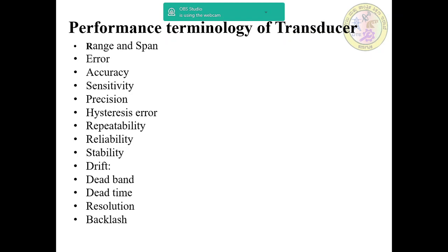Next is dead time. It is the time required by the transducer to begin to respond to a change in its value. Next, resolution. Resolution is defined as the smallest increment in the measured value that can be detected. It is the smallest change in the input value which will produce an observable change in the output. Last one is backlash.